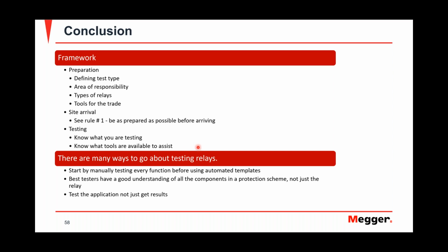And the last advice I would give for new relay testers or engineers is start by manually testing every function before using the automatic templates. Try to understand the function, the test set, the software and the tools. The best testers have a good understanding not only of the relay, but the whole protection scheme. So you don't have to be an expert on everything, but have general knowledge, or acquire it as you progress in your career.